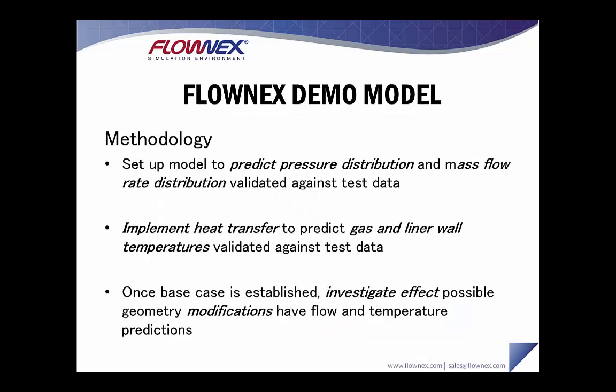The methodology for setting up a Flownex model is to first predict pressure distribution and mass flow rate distribution and validate that against test data. Then one would implement heat transfer to that cold flow model to predict gas and liner wall temperatures and again validate those results against test or CFD data. Once the base case is established, the effects of possible geometry modifications can be investigated to see how they affect both flow and temperature.